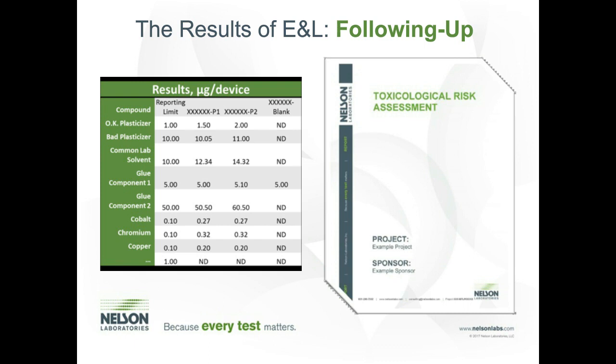We talked about new and upcoming biocompatibility concerns. This gas path standard is new in the industry. It's something that is starting to be enforced by all regulatory authorities. We're seeing a big push for this, and so we wanted to make people aware if you fit into that category. But really, the results are evaluated just like any other medical device toxicological assessment. The only difference is you have to look at the route of administration, which isn't really a difference, but most devices aren't meant to be inhaled. In this case, the compounds will have an inhalation endpoint, and so the toxicology assessment needs to be evaluated for that endpoint. But once you have those evaluations, then you can really determine the safety.